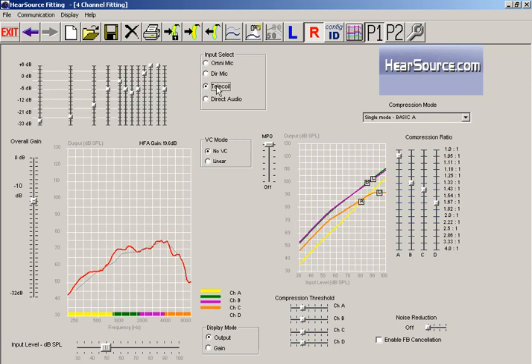Now when you take a telephone and put it up to the hearing aid while it's using this telecoil, it draws the signal right out of the receiver headset of the telephone and brings it into the hearing aid, amplifies it, and then kicks it into your ear. One of the major problems when you try to use a microphone with a telephone is sometimes you get a lot of feedback and whistling, and by shutting off the microphone and just using the telecoil you eliminate that. You get more of a cleaner direct input.